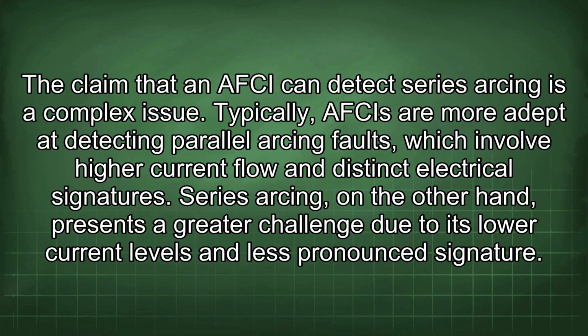The claim that an AFCI can detect series arcing is a complex issue. Typically, AFCIs are more adept at detecting parallel arcing faults, which involve higher current flow and distinct electrical signatures. Series arcing, on the other hand, presents a greater challenge due to its lower current levels and less pronounced signature.